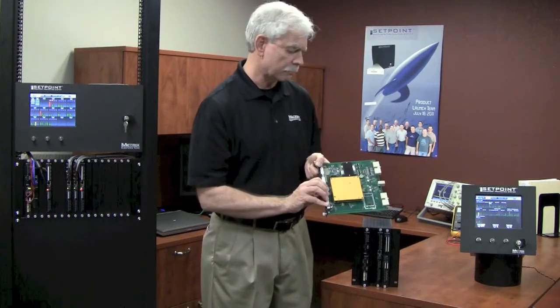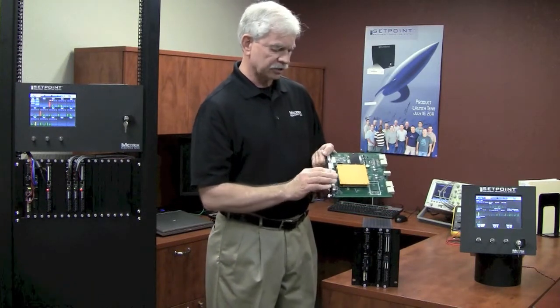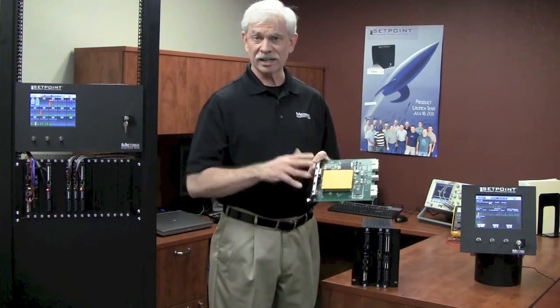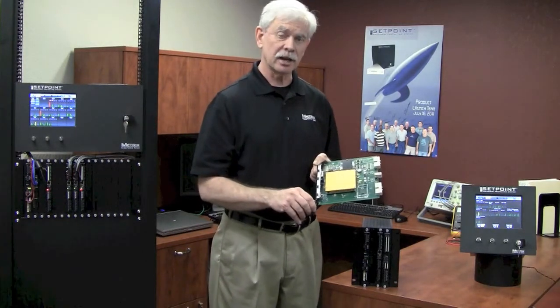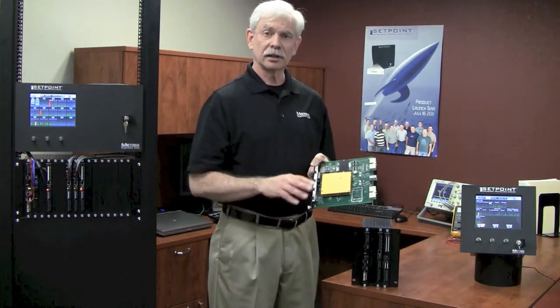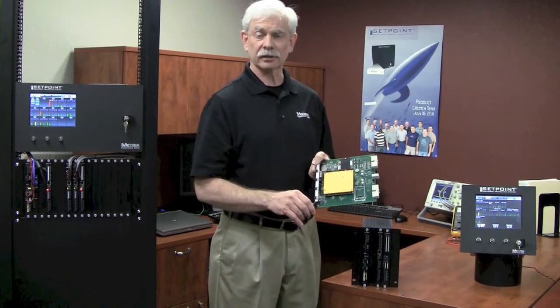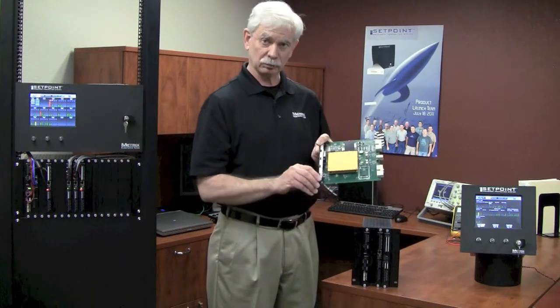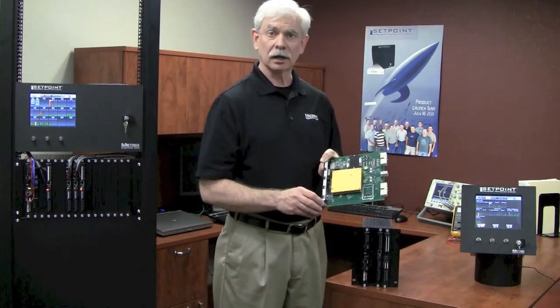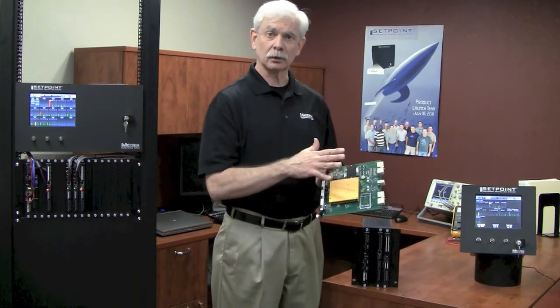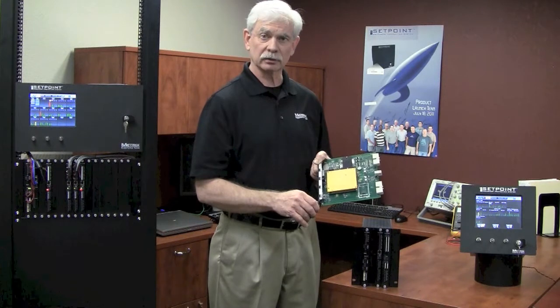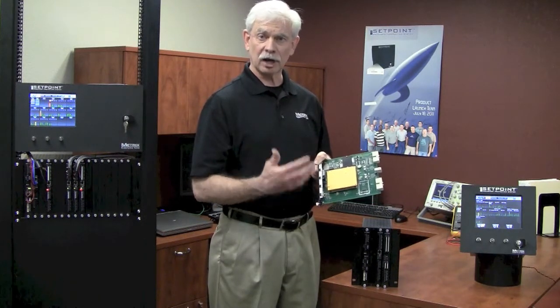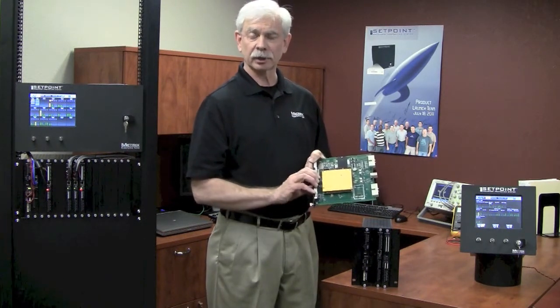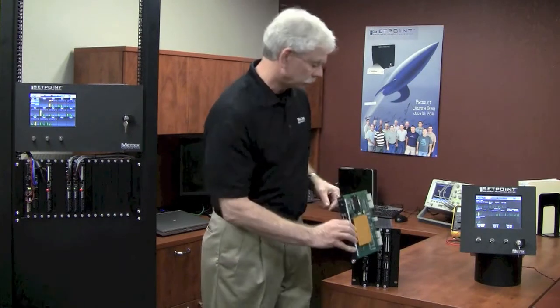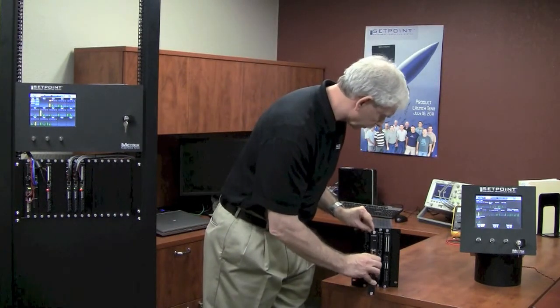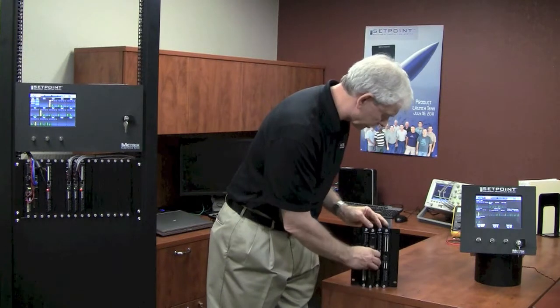SETPOINT CMS client. So the SAM is basically an optional module because it's providing communications type activities and not machinery protective functions. It is not designed to be in the critical path of the machine protection system. So we could pull the SAM out of the rack, or a processor could fail, or some other component on the board could potentially have a problem, and it would not affect the ability of our rack to protect the machine. The next module type we'll take a look at is our Universal Monitoring Module.